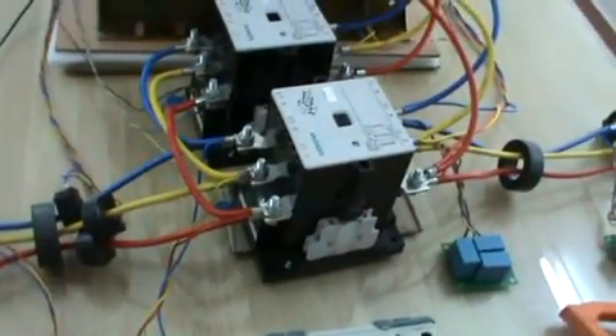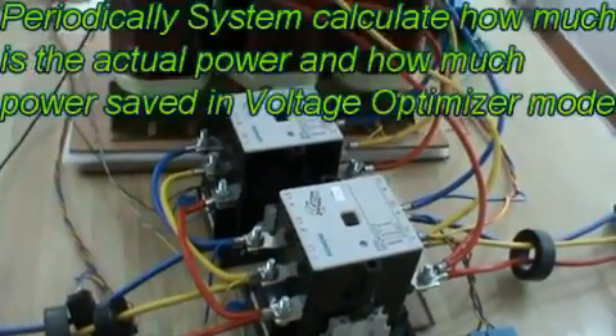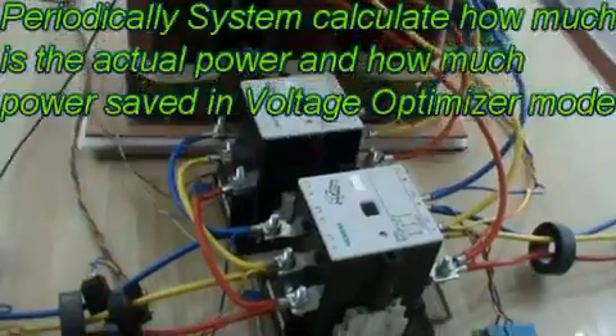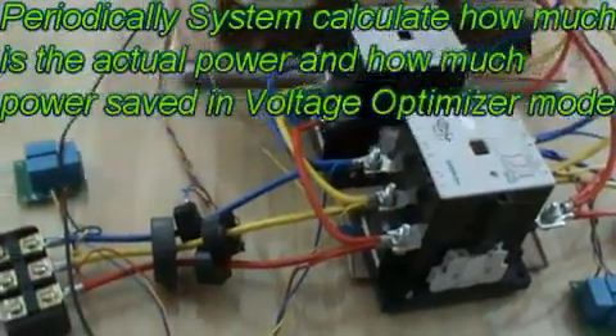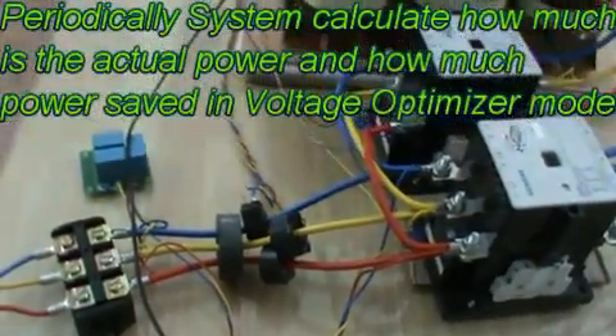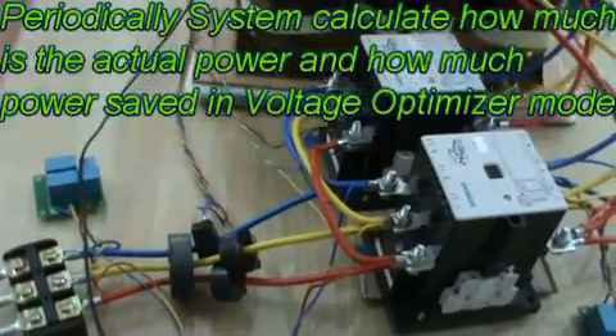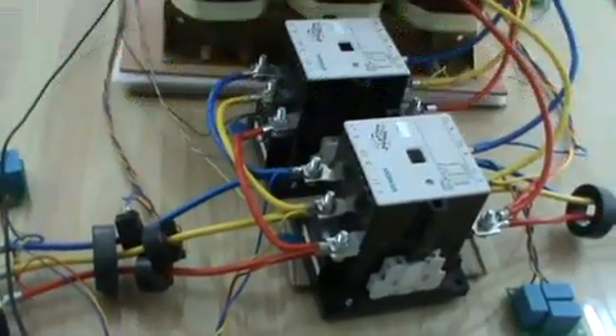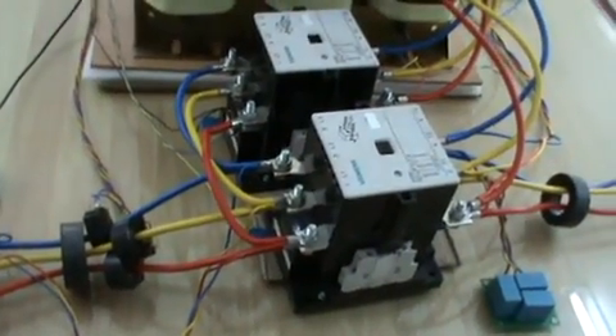Now it is operating in VO mode, voltage optimizer mode. The system will go every 1 hour or half an hour to bypass mode and see how much is the actual power consumption, and it will go back to voltage optimizer mode and calculate how much are the savings.